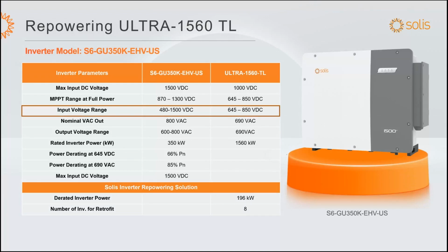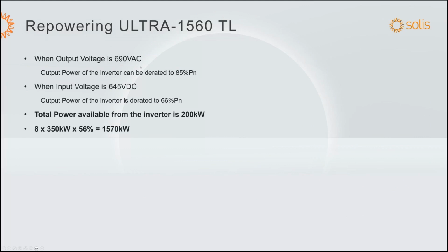We can look at the input voltage range. So this inverter can cover the required input voltage range for the Ultra inverter with some derating. And then the output voltage range, it is rated 300 kilowatt at 690 volt AC. So it could cover the output voltage range as well. And it will take 8 inverters derated to 196 kilowatt to replace an Ultra inverter. And that's where the 690 volt, it will be 85% of nominal power of 350, so it's about 300 kilowatt.